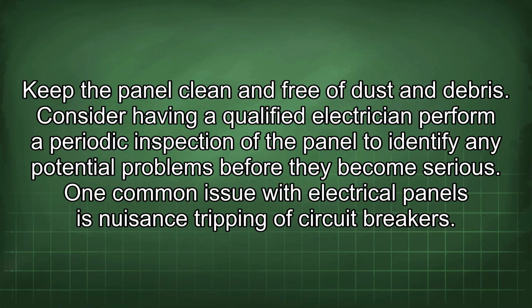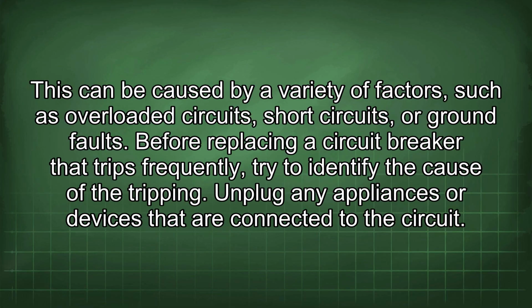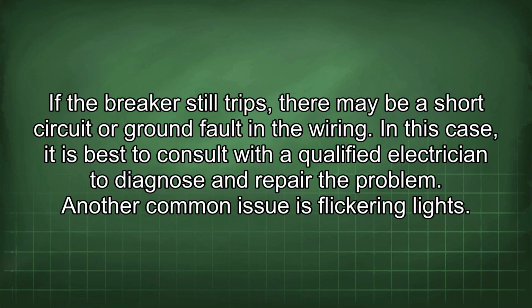serious. One common issue with electrical panels is nuisance tripping of circuit breakers. This can be caused by a variety of factors, such as overloaded circuits, short circuits, or ground faults. Before replacing a circuit breaker that trips frequently, try to identify the cause of the tripping. Unplug any appliances or devices that are connected to the circuit. If the breaker still trips, there may be a short circuit or ground fault in the wiring. In this case, it is best to consult with a qualified electrician to diagnose and repair the problem.